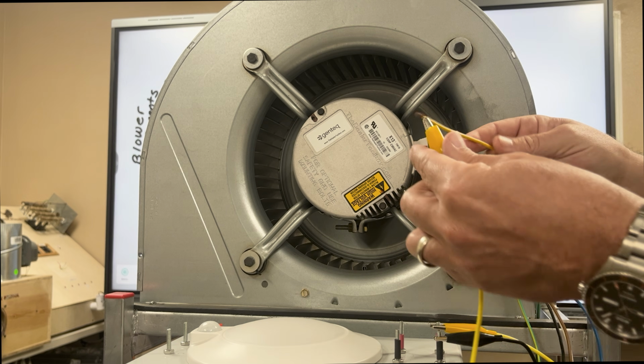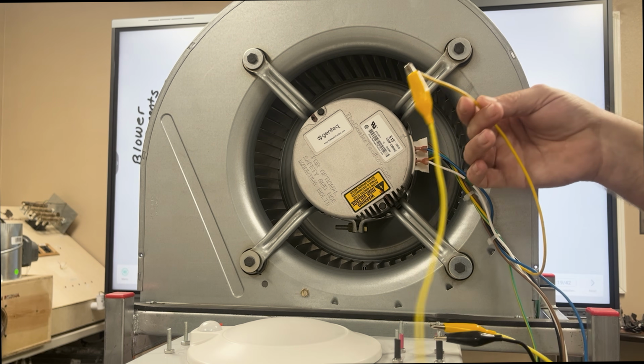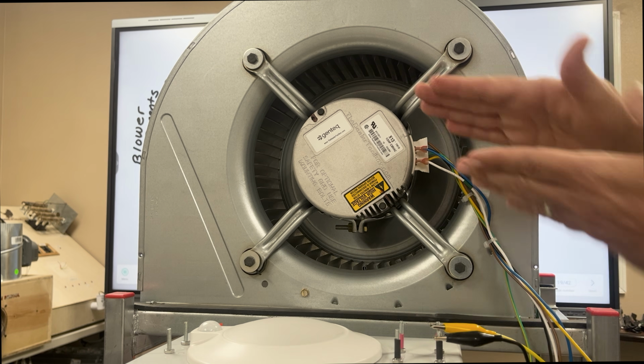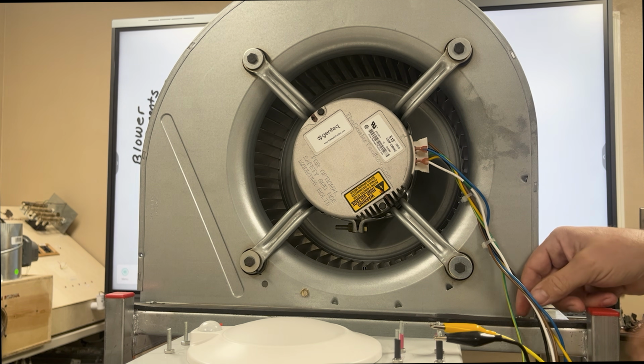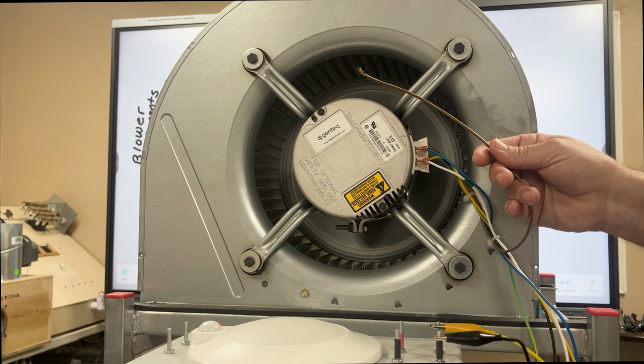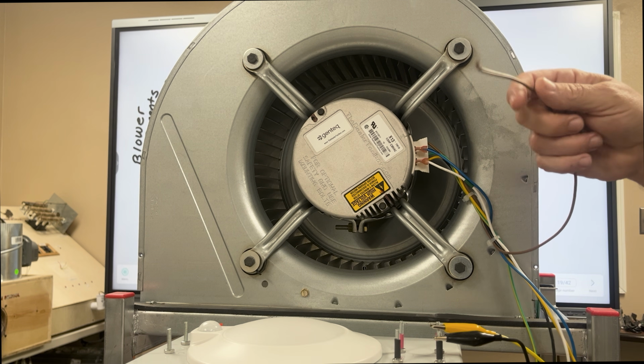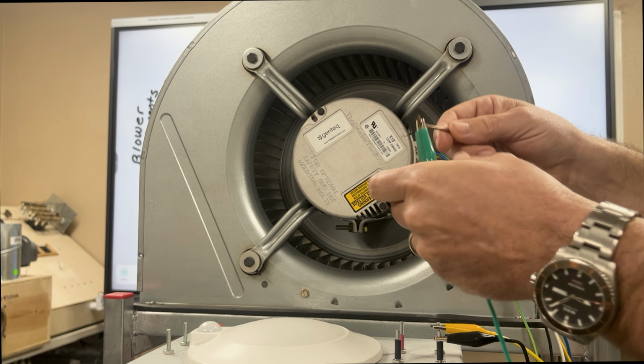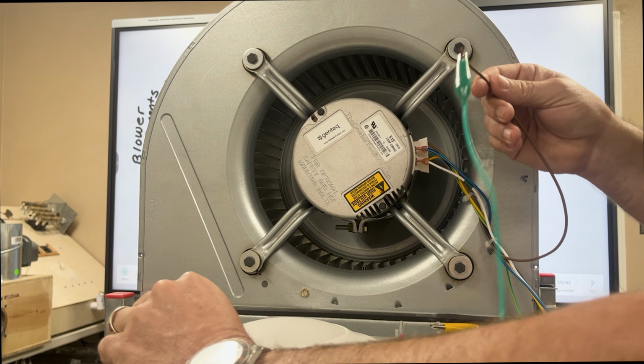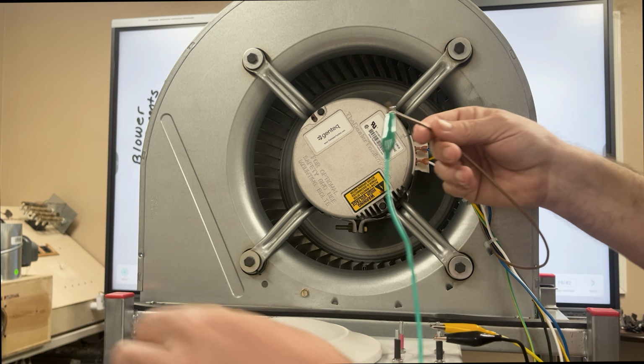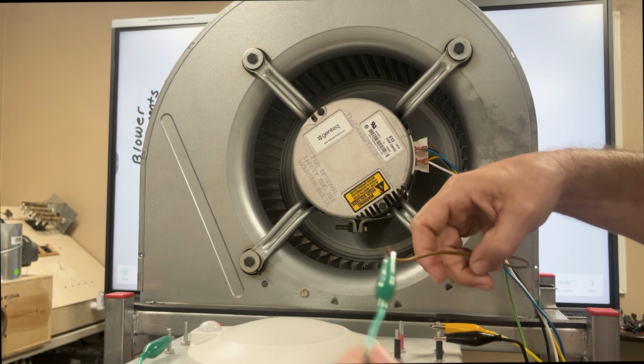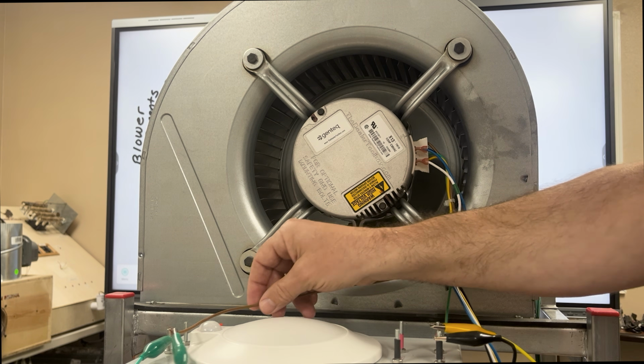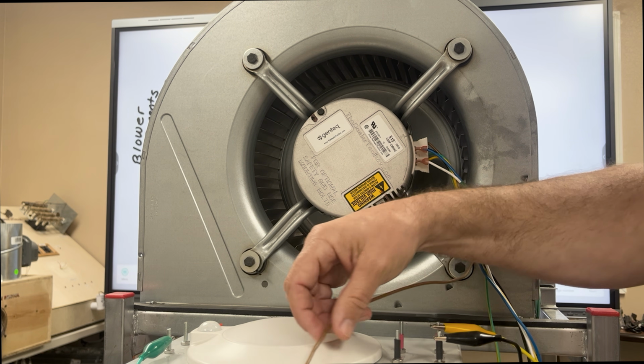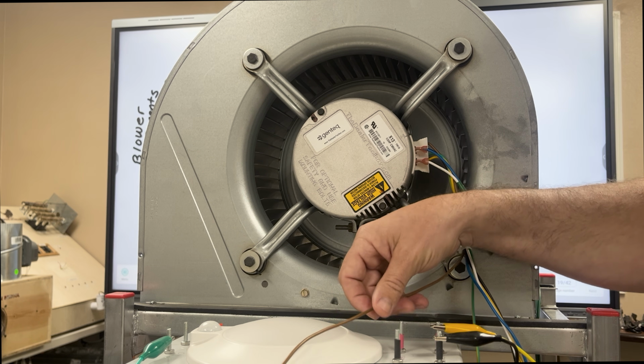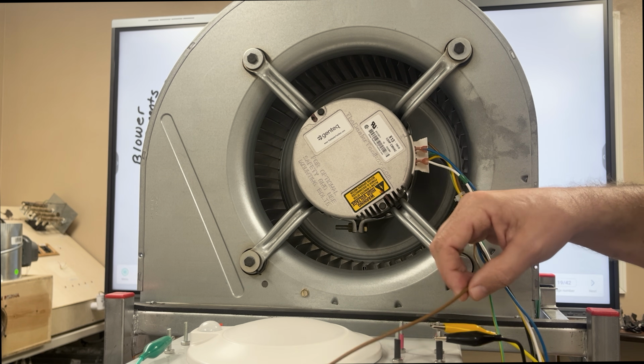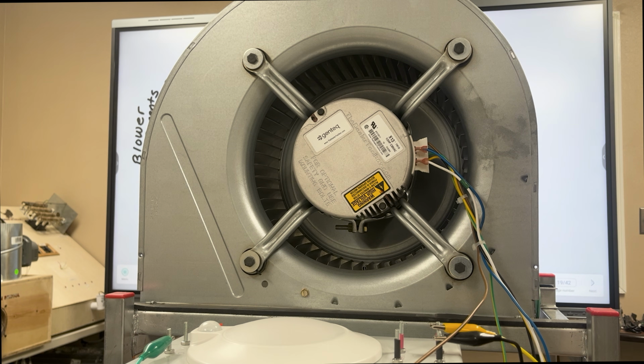And we're going to wire it up to our other high voltage leg of our motor. Now we have 230 volts on this. We have to give it a common, a low voltage common. So I'm going to wire low voltage common. We're going to put that on the common side of our transformer. Okay, I'm going to let this one hang down on this end over here carefully. We don't want that to touch anything. At least we don't want it to touch the high voltage. Let's see where it's going to fall. That's safe.